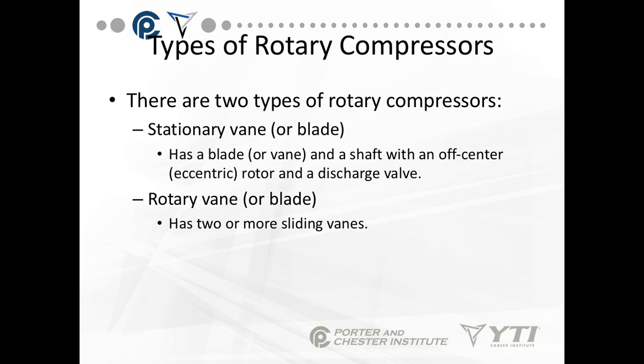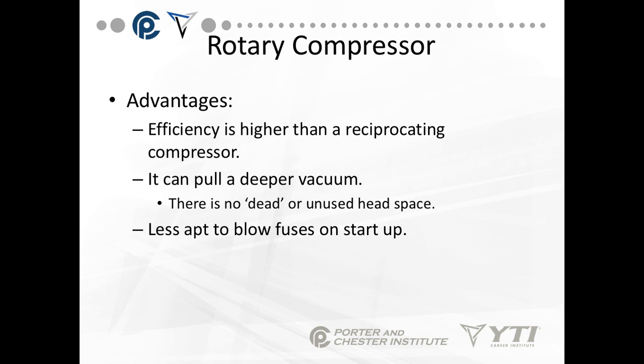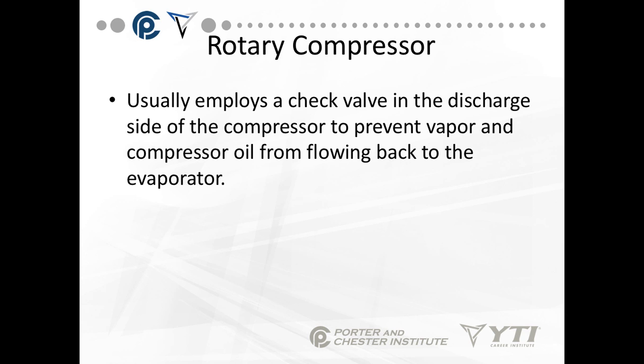There are two types of rotary compressors. One is called a stationary vane or blade — it has a blade or vane, a shaft with an off-center rotor, and a discharge valve. The rotary vane or blade has two or more sliding vanes. The advantages of a rotary compressor: efficiency is extremely high, much higher than a reciprocating compressor. It can pull a deeper vacuum because there's no dead or unused space. It's less apt to blow fuses on startup since we have a rotating device rather than a piston. You'll find rotary compressors frequently in residential air conditioning systems. They usually include a check valve on the discharge side to prevent vapor and compressor oil from flowing back to the evaporator.